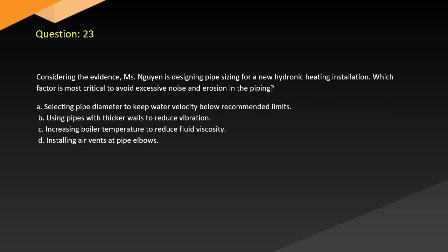Question 23. Considering the engineer is designing pipe sizing for a new hydronic heating installation, which factor is most critical to avoid excessive noise and erosion in the piping? A. Selecting pipe diameter to keep water velocity below recommended limits. B. Using pipes with thicker walls to reduce vibration. C. Increasing boiler temperature to reduce fluid viscosity. D. Installing air vents at pipe elbows.